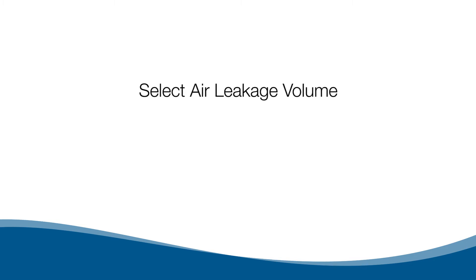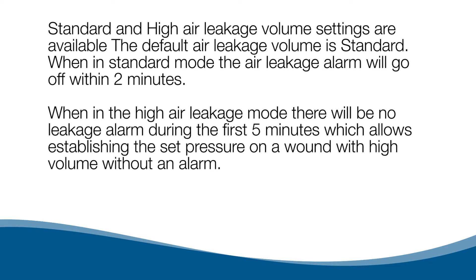Select air leakage volume. Standard and high air leakage volume settings are available. The default air leakage volume is standard. When in standard mode, the air leakage alarm will go off within 2 minutes.